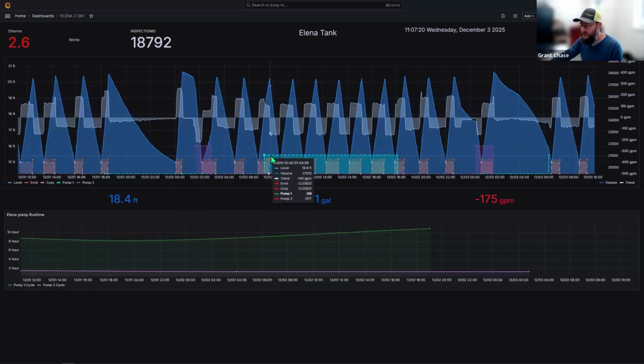We've got pump indications. If you notice the tooltip, I can highly customize the end product of Grafana to where I can give custom names to the level, the units for the level, the trend, the valve position mapped to open and closed. So you can see those changing, even colors changing - green for open or on, and red - all within the tooltip as you move through time.